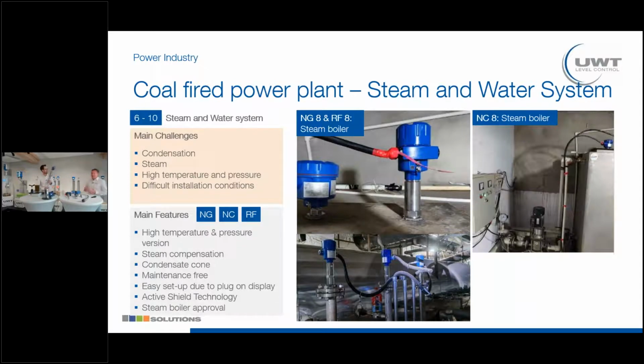We do have a steam compensation, a special feature. So when we have a lot of steam inside the steam boiler, then we have the steam compensation to get accurate measurement results. You can install it also in bypass, so pretty flexible to use here, and in combination with the RF8, our point level sensor, we do again have this redundant system for the steam and water system. So also Nivo Kappa would be a solution if the temperature and pressures are not that high. Nivo Kappa could also work.